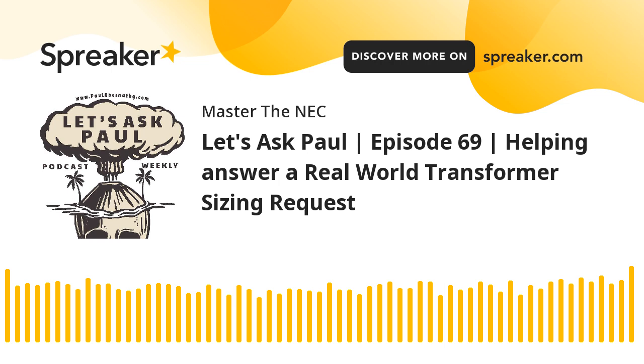Again, some engineers will say, no, I need more capacity. I need to have a buffer. And I know plenty, and I'm just telling you from experience, who will look at the next available size transformer and bump you to it and say, okay, I want you to go to a 45. And you're going to get some extra capacity out of it. And maybe you're going to do it like I told you. Maybe you're going to install a NEMA 3R panel, and that way you have the ability to get other loads out of it.